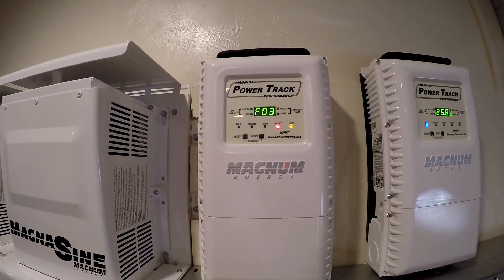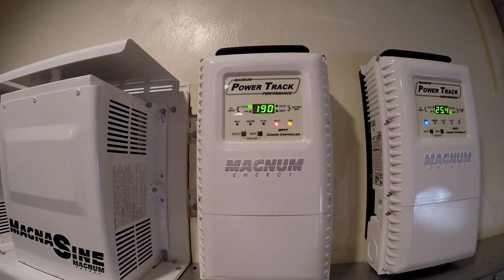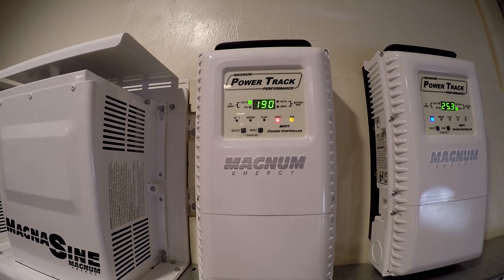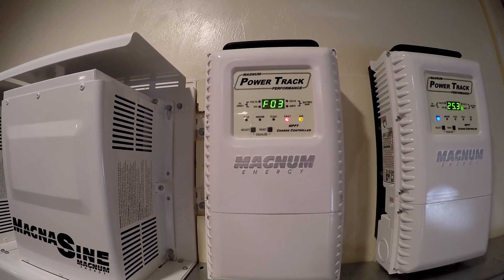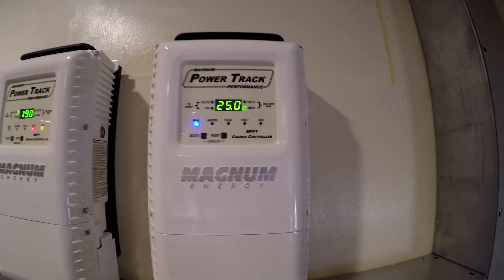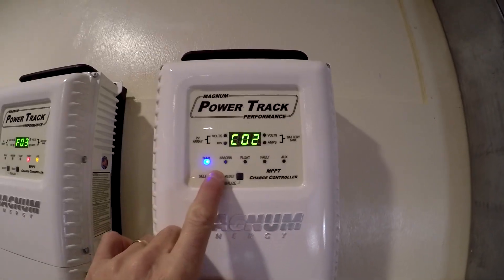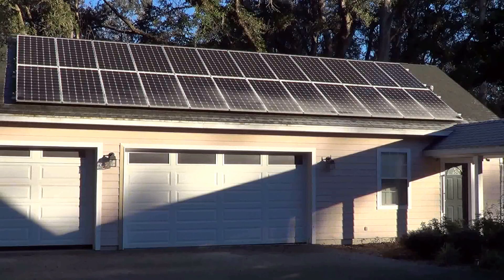Cold temperature, high sun — and 190 volts is not too high for this system. I have to look up fault F03. The bottom row is still good. Let's see what kind of voltage we have there — 166 volts, but it's still got frost on it.